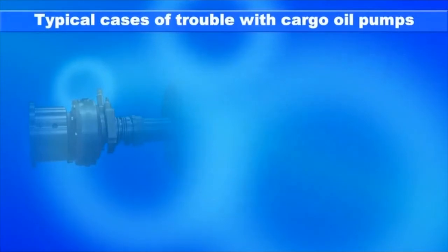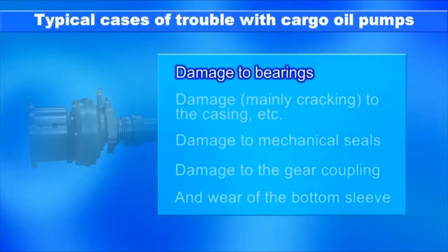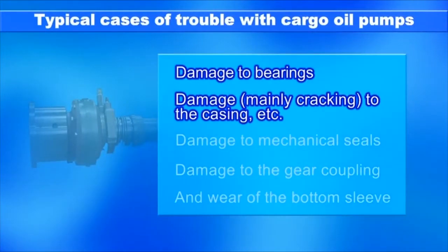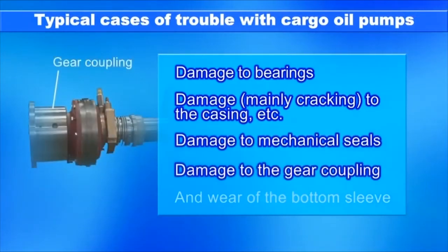The following are typical reported cases of trouble with cargo oil pumps: damage to bearings, damage mainly cracking to the casing, damage to mechanical seals, damage to the gear coupling, and wear of the bottom sleeve.